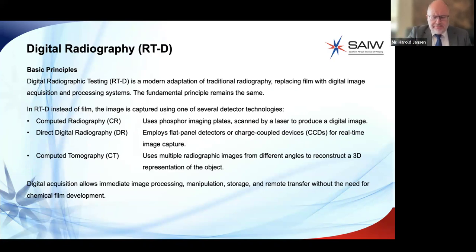Digital radiography testing is a modern adaptation of traditional radiography, replacing film with digital image acquisition and processing systems. The fundamental principle remains the same. In other words, X-rays or gamma rays are directed through the test object, and the transmitted radiation is captured to produce an image that reveals internal features based on variations in the material thickness, density, as well as composition.